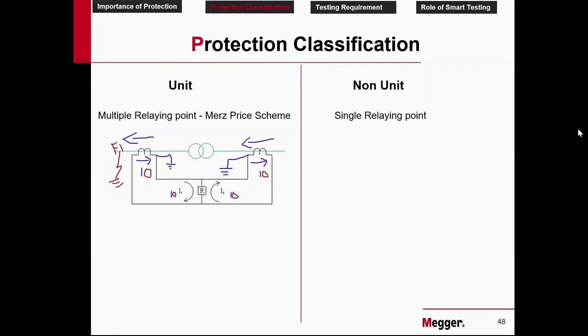Let us see a third example. I will make another color. This time, let me make it pink. Okay, a fault occurs here. Fault at F2. When this fault occurs here, this direction changes. Because fault current always chooses the least resistance path. This already flowing towards the fault, this current also starts flowing towards the fault. So if the primary current flows from left to right like this, winding towards, the secondary also will change the direction. So now this direction will become like this.